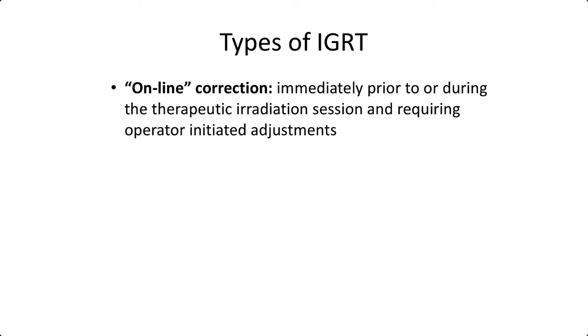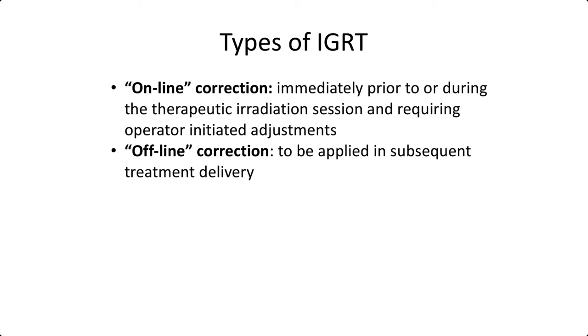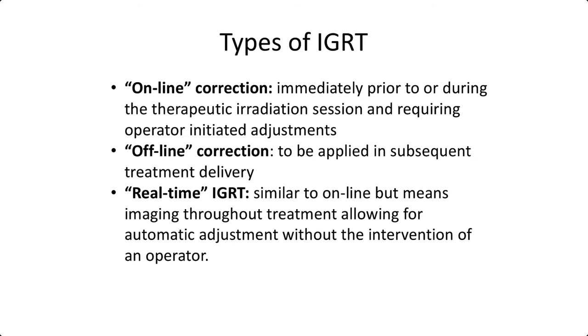IGRT can be used in several ways. Online corrections are performed immediately prior to or during the radiation session and require an operator to initiate adjustments. Offline corrections involve imaging that is applied at the next treatment session. Real-time IGRT is similar to online but involves imaging throughout the entire treatment, allowing adjustment of patient position during treatment — typically automatic and sometimes without operator intervention.